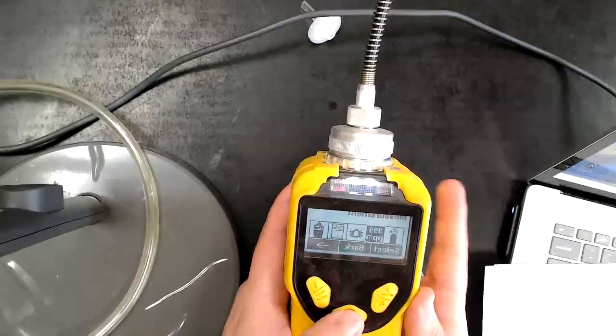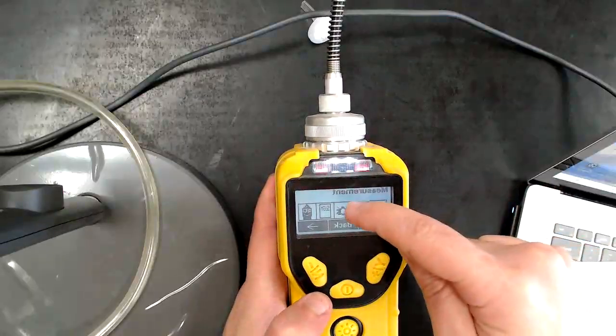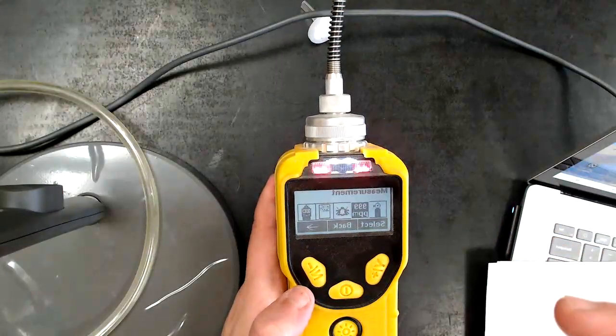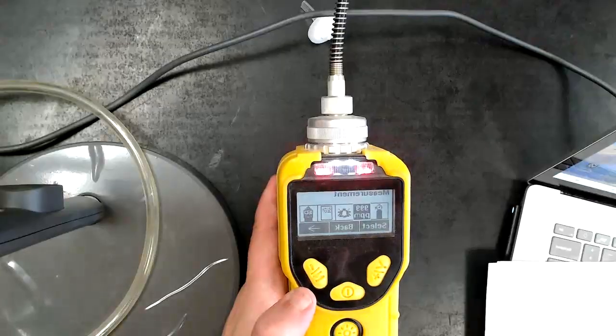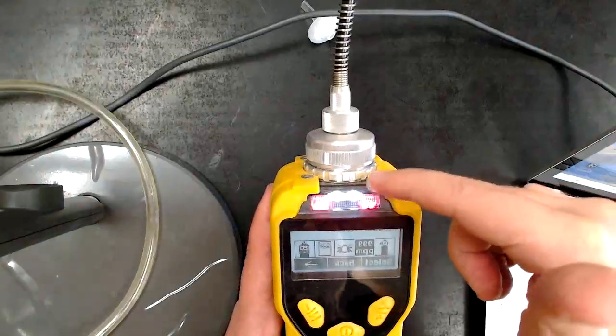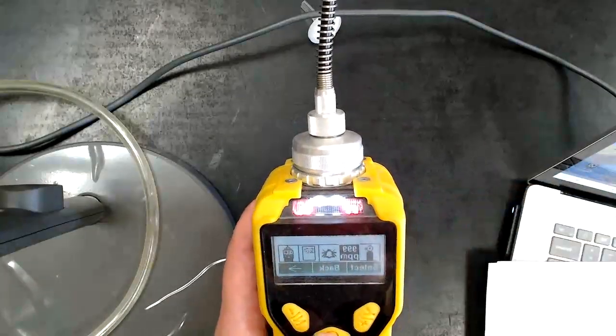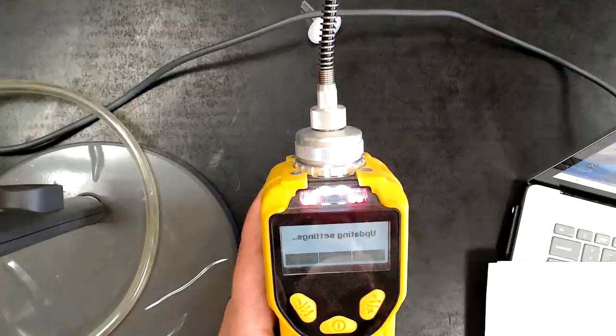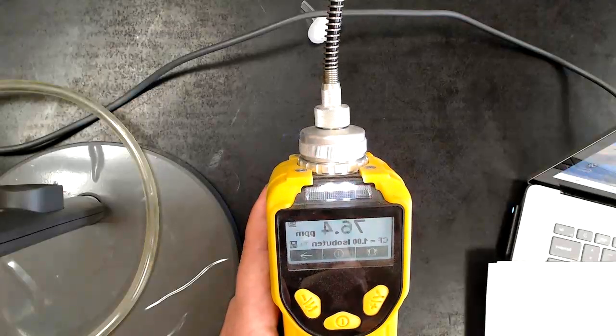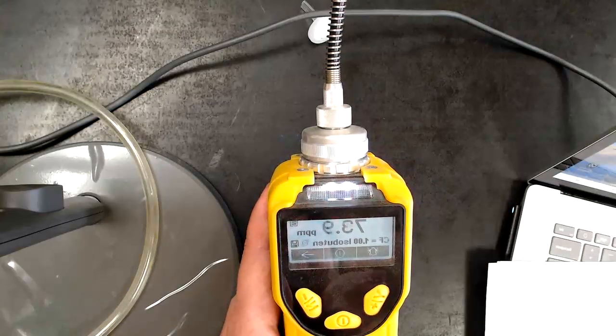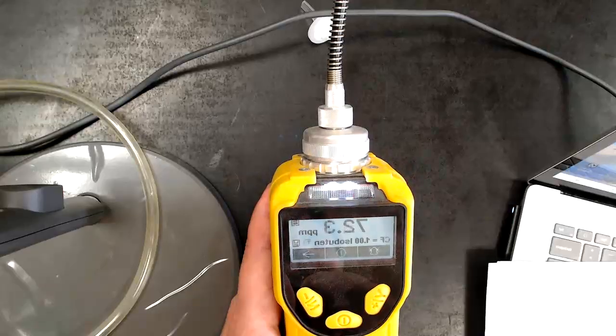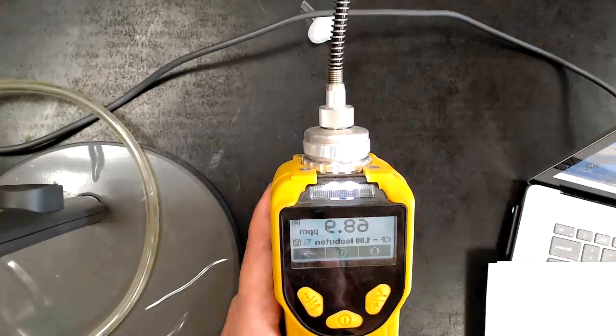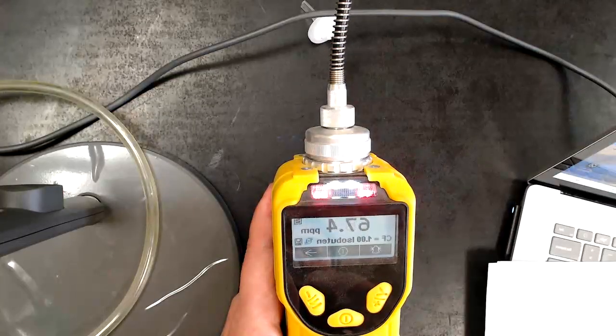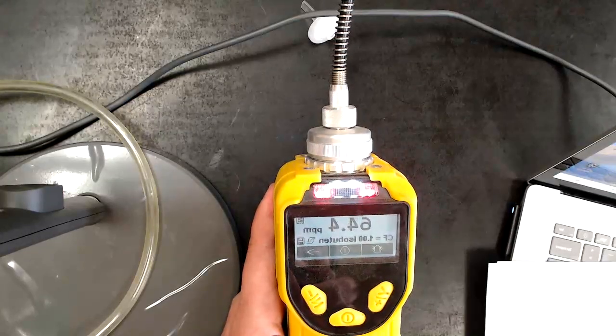Then we can have other settings, like the alarm feature. It was reading the isobutylene, which is why we got the alarm state. Now it's going to update. It takes a little bit to equilibrate. Even though we have the span gas off, it's still registering that in the air a little bit. After a couple of minutes, it's going to go back down to zero.